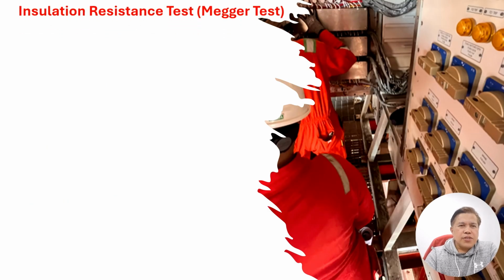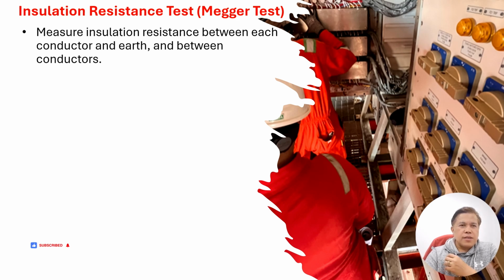So what is the insulation resistance test? You use a Megger to measure insulation resistance between each conductor. So meaning you are installing your cable run from a JB to another distribution board, or from a distribution board going to the junction box. These cables need Megger testing.